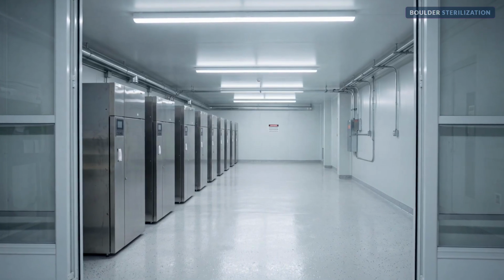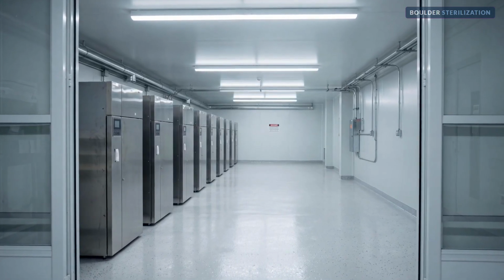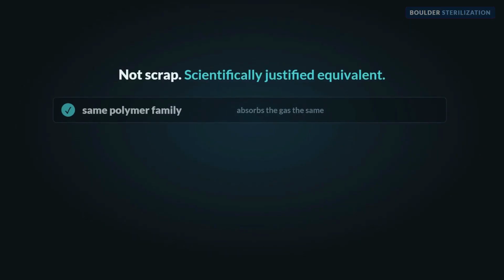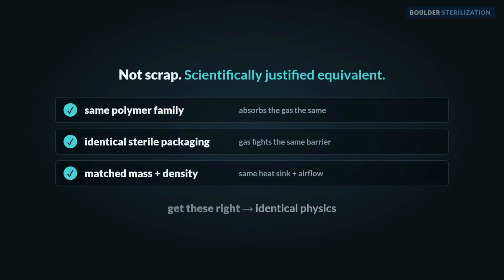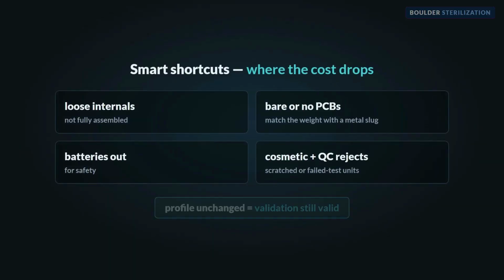But it only counts if that behavior is provably equivalent. Dunnage can't be scrap cardboard and packing peanuts. It has to be scientifically justified. The same family of plastics as your device, because the resin is what absorbs the gas. The exact same sterile packaging, the same pouch or tray, because the gas has to pass through that same barrier to reach it. And matched mass and density so it sinks heat and chokes airflow like a real full load. Get those right, and the physics inside that chamber are identical.